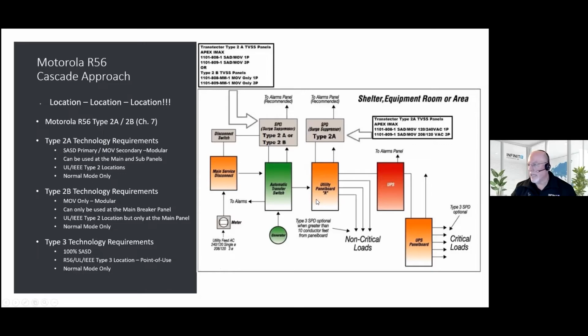This shows you what's called a cascading surge protection plan. So there'll be a surge arrestor at the main panel, usually in front of an automatic transfer switch, protecting the ATS. And then they'll have another surge arrestor at critical sub panels that feed power to the 19-inch racks with the radios in them. And then they'll also have the Type 3 plug-in stuff. The reason for that is that lightning will attach itself and induce surge currents on all conductive cables in the lightning sphere. Now a lot of people say, well, I need a whole facility protector, which is the main panel. Okay, we can do that. But if your critical $100,000 piece of gear is at the other end of the factory, 300 cable feet away from the main entrance, then that main entrance protector is not going to protect your equipment 300 feet away because of induced surge currents. So you'll need to put another surge protector somewhere else.